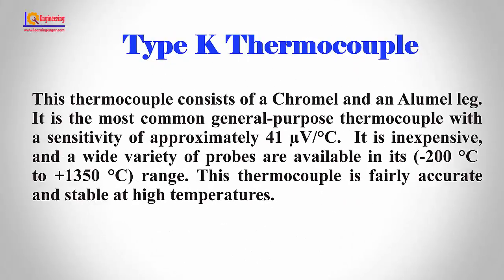Type K thermocouple. This thermocouple consists of a chromel and an alumel leg. It is the most common general-purpose thermocouple with a sensitivity of approximately 41 microvolts per degree centigrade.